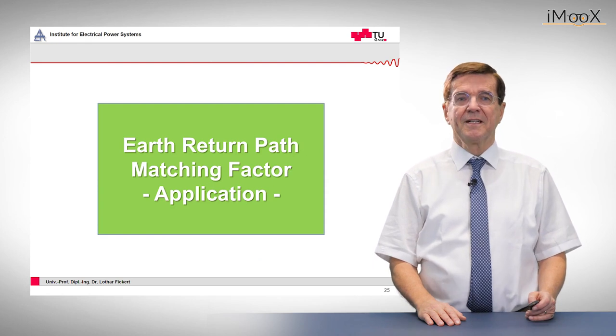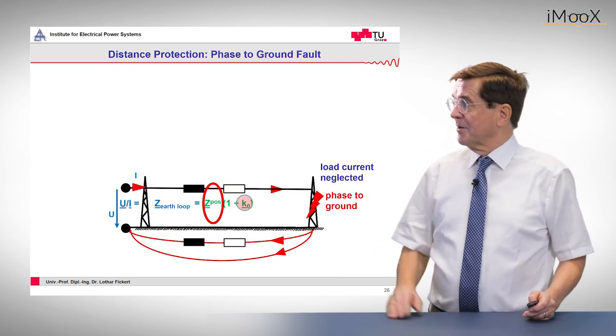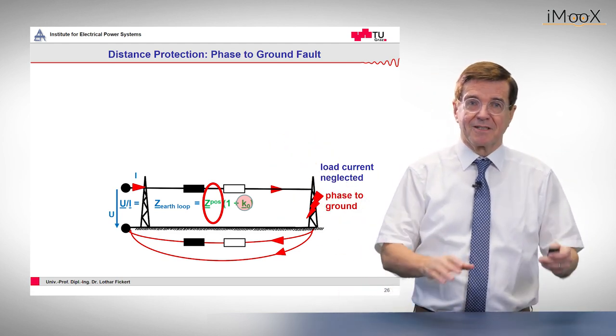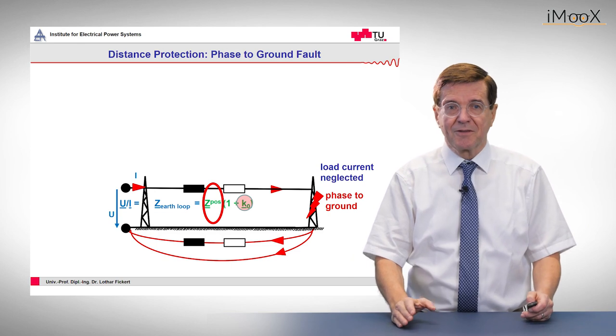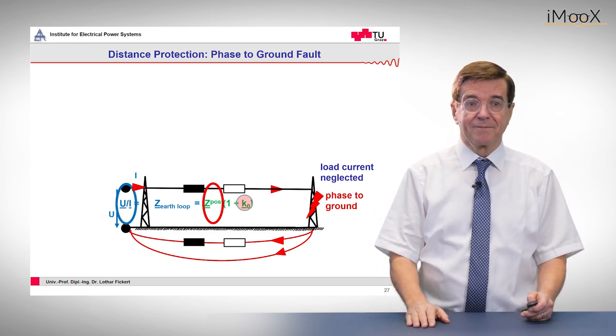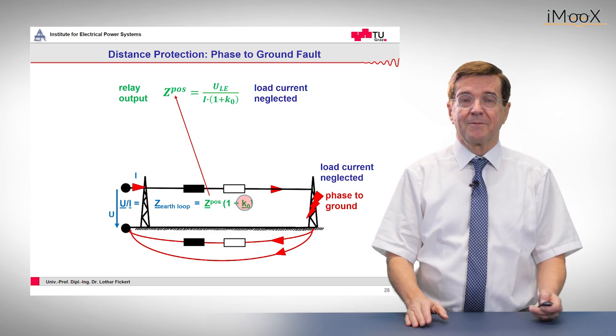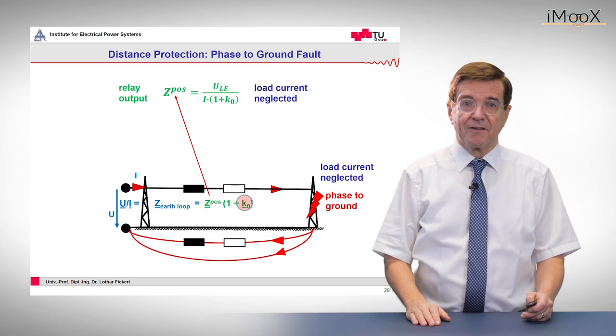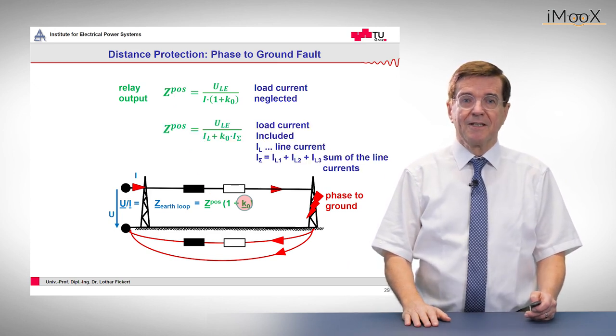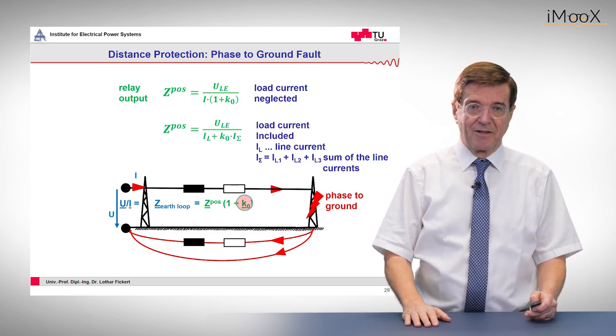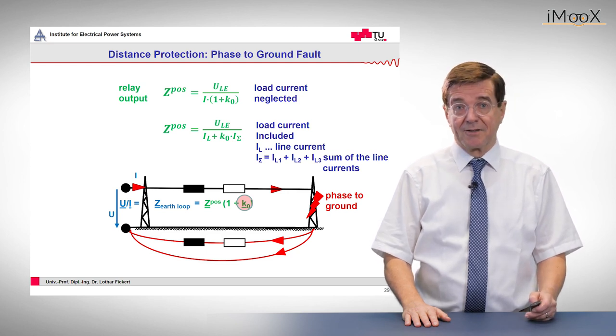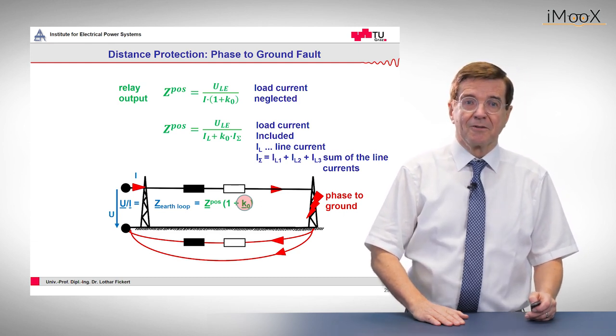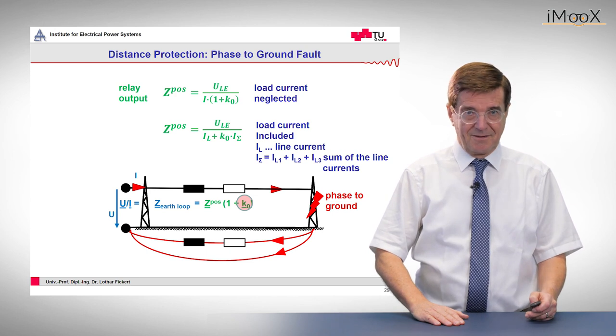The application is: we want the positive sequence impedance, which is the line impedance from the relay to the fault, but we measure the loop impedance. The loop impedance can then be calculated back by applying this formula when we neglect the load current. If we take substantial load current into account, the formula is slightly modified — we include the line current and, multiplied by this earth return path matching factor, multiplied by the sum of the line currents.